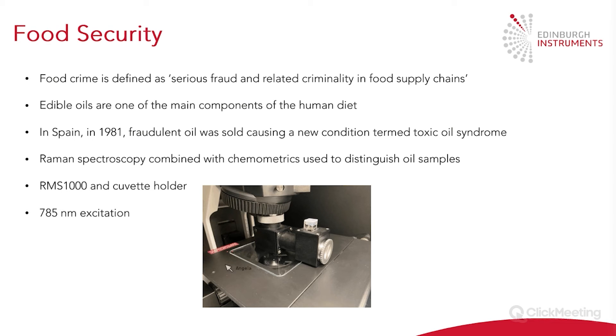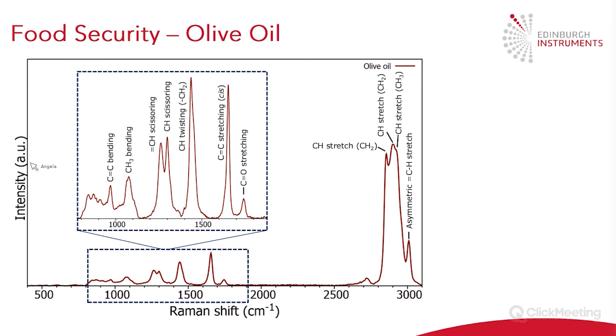In this case the RMS1000 was fitted with a cuvette holder with an x10 objective and the laser light focused onto the cuvette. I used 785 nanometer excitation because one of the oils was coloured chilli oil, so using a visible laser gave too much background fluorescence. Here we see a typical spectrum of olive oil, which can be split into two sections: the high wavenumber region and the fingerprint region. For most samples, the fingerprint region is the region of interest, as there are more peaks which are better defined, giving more information for identification.